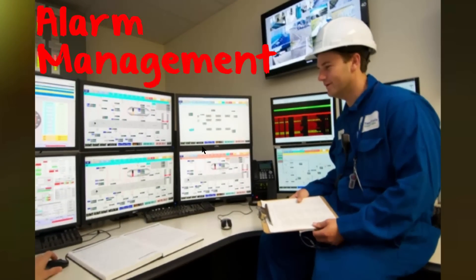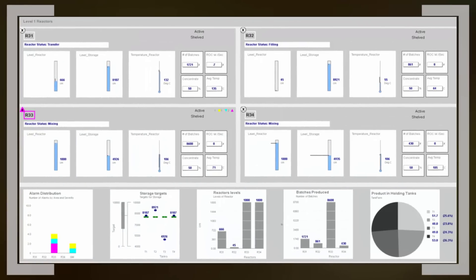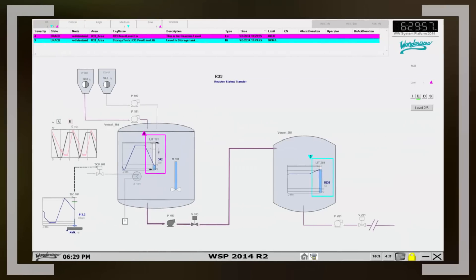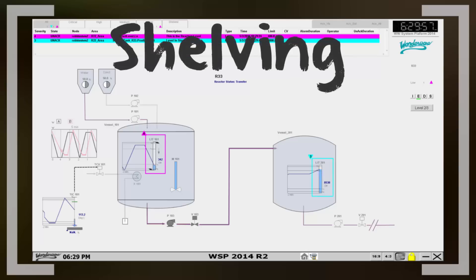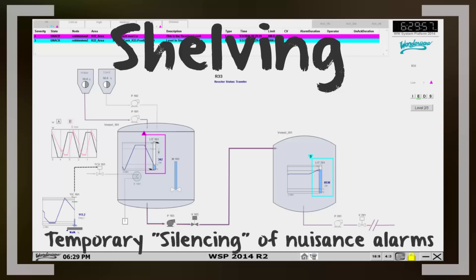Any system that is engineered properly must also have a good alarm management strategy. This screen depicts an operator that doesn't appear to be paying much attention to the alarm grid even though it seems to have many active alarms — that can be the case in systems where alarm management is poor. In this release, we have delivered additional functionality to assist with a better alarm management strategy. For over a year now, we have been promoting the HMI design paradigm of situational awareness. It is very important for an HMI-driven system to be providing the correct information, otherwise the operator stops trusting it. There are cases where field equipment is faulting causing nuisance alarms. We have added the shelving functionality to the software, allowing the temporary silencing of nuisance alarms so operators can focus on actual tasks instead of being distracted.